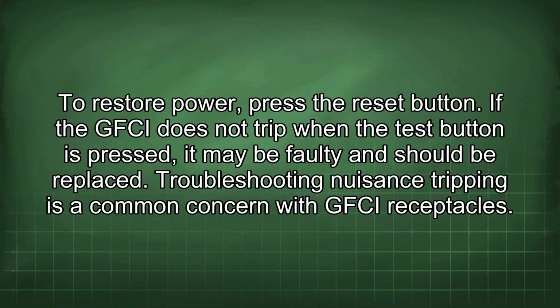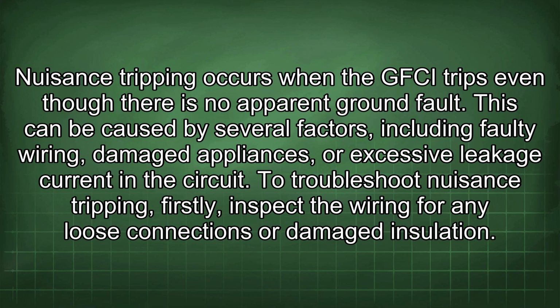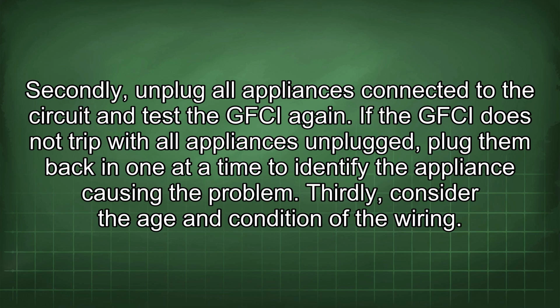Troubleshooting nuisance tripping is a common concern with GFCI receptacles. Nuisance tripping occurs when the GFCI trips even though there is no apparent ground fault. This can be caused by several factors, including faulty wiring, damaged appliances, or excessive leakage current in the circuit. To troubleshoot nuisance tripping, firstly, inspect the wiring for any loose connections or damaged insulation. Secondly, unplug all appliances connected to the circuit and test the GFCI again. If the GFCI does not trip with all appliances unplugged, plug them back in one at a time to identify the appliance causing the problem.